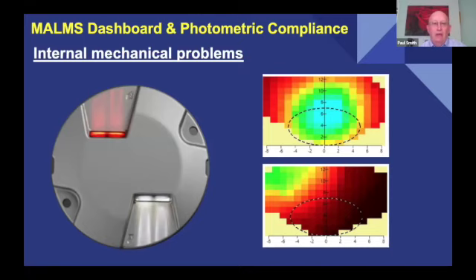And as an example, if that bottom fixture was a halogen inset center line, my guess is that the halogen lamp either has a broken reflector or isn't seated properly, which is why it's shining off quite brightly, but at the wrong angle. Okay, thank you. And I would deduce that without even taking the fitting apart. I could be wrong, but 9 times out of 10, that would be the first thing I would look for.